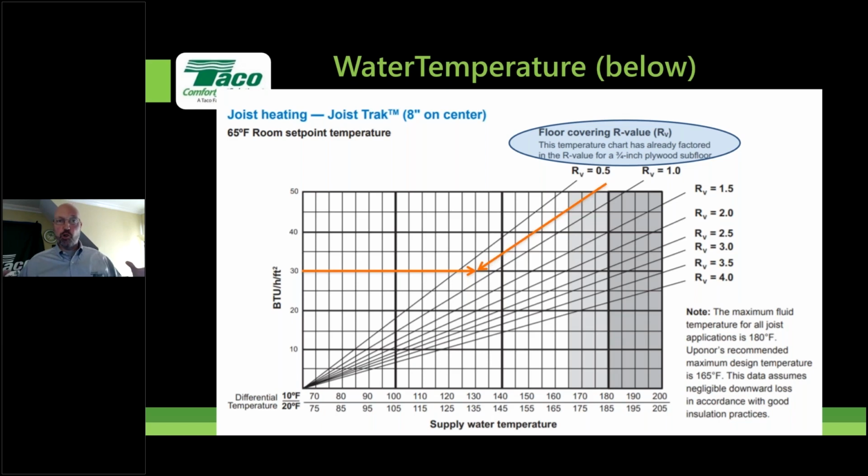All right, you can group those two together because the water temperatures are close. If you had one room at 100, another room at 130, then you're probably not going to group them together. And as Rick and John were saying before, add more zones to an application, a different thermostat, because the heat load BTUs per square foot may be different. So there's a lot of variables that come into play when you start grouping rooms together based on water temperature also.